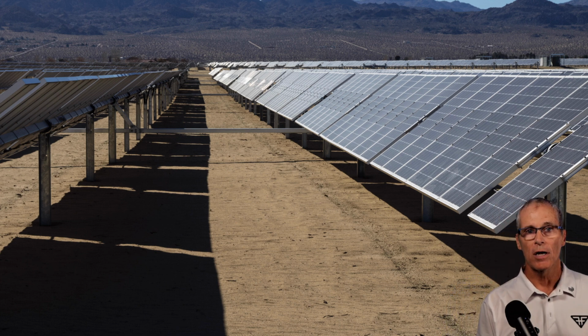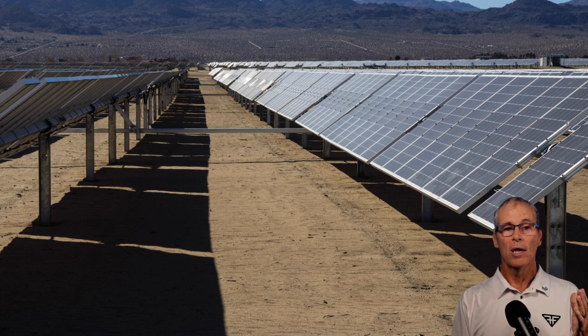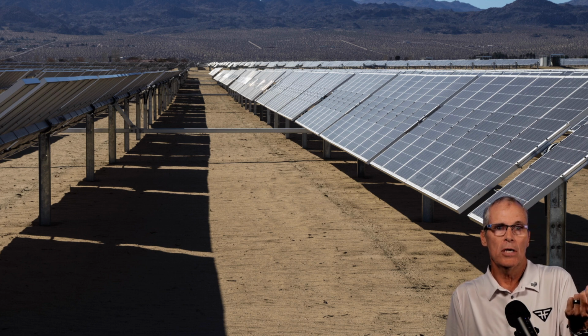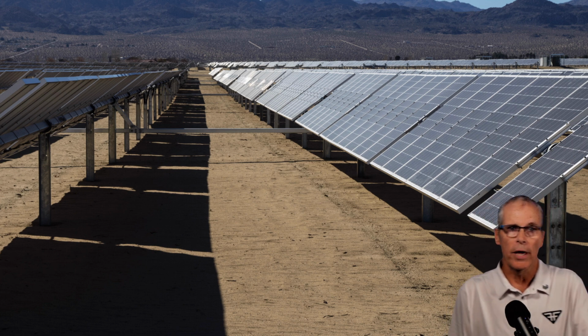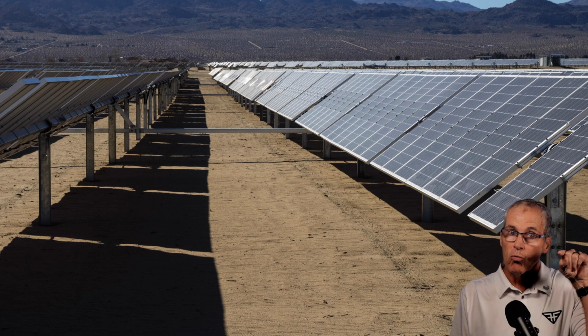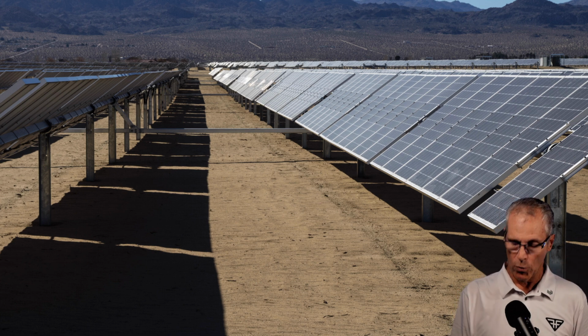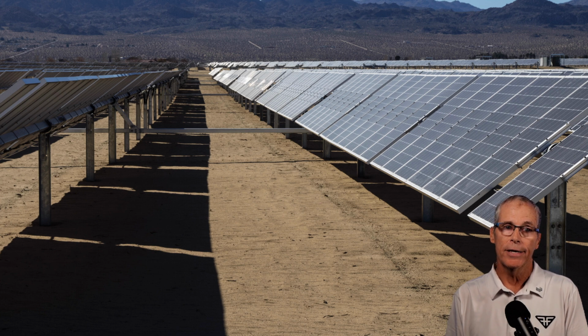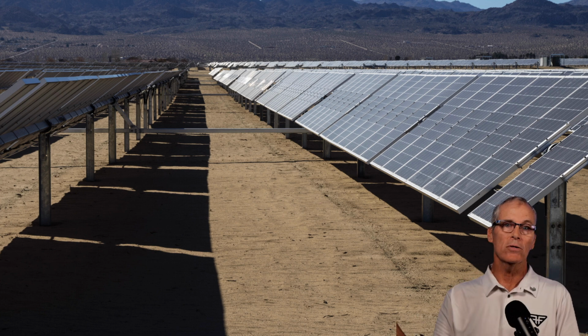Again, it's not going to be the kind of thing that you go out and replace all at once, but this is more likely to lead to an issue than just having a mismatched connector sitting there with only the heat up and cool down of the air temperature around it to really cause it to move. The ones that are rubbing around those track supports, those are the ones I'd be careful about looking at. And again, it's going to be hard to replace them because there's thousands of those.